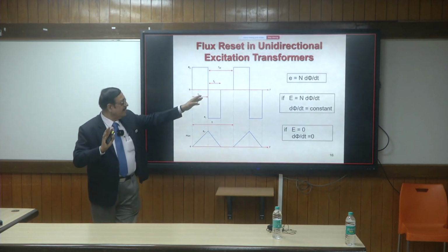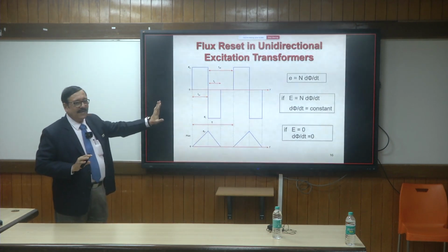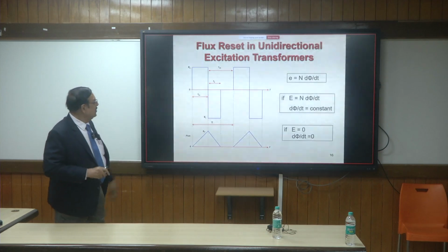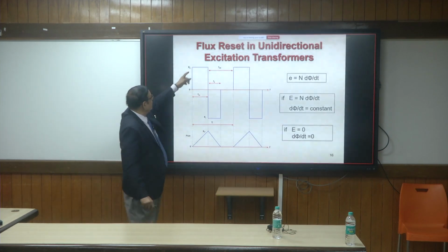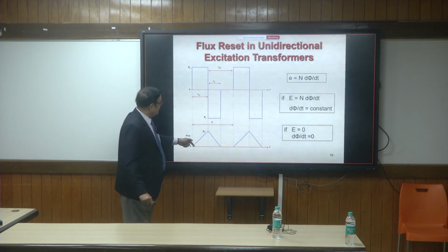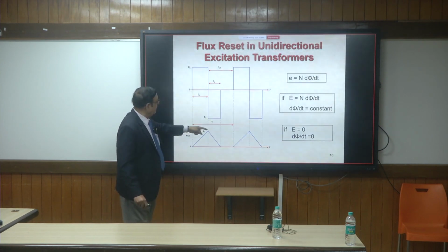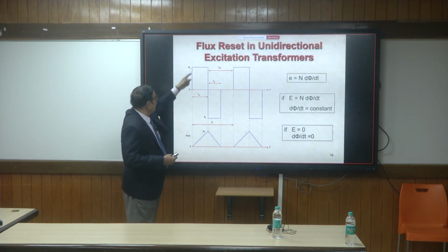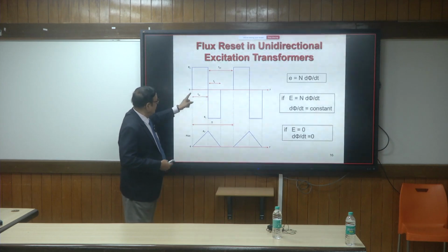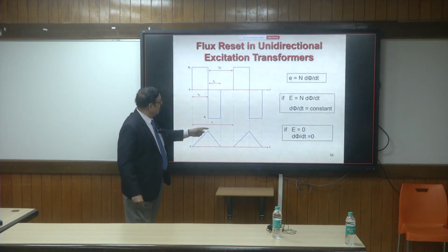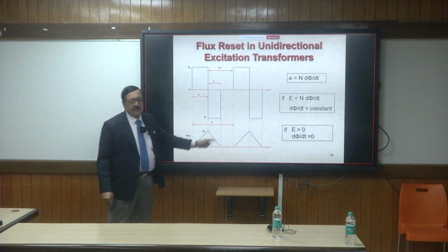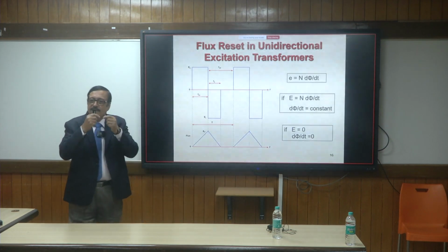So you have to understand the interpretation of the waveforms, and that's exactly what happens. When we apply a DC voltage to a transformer, the flux rises up to a value of phi m, wherever, depending on the magnitude of voltage and the time applied. And if you make it 0, the flux will remain at that point, so you have to bring the flux down again.